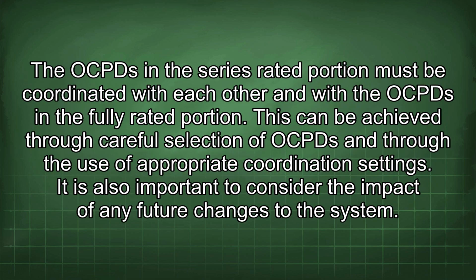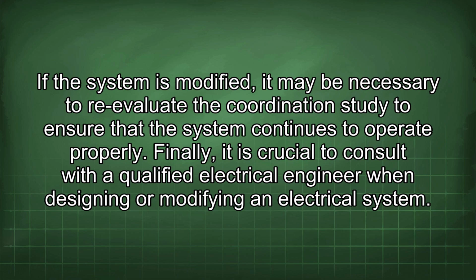The OCPDs in the series-rated portion must be coordinated with each other and with the OCPDs in the fully rated portion. This can be achieved through careful selection of OCPDs and through the use of appropriate coordination settings. It is also important to consider the impact of any future changes to the system.